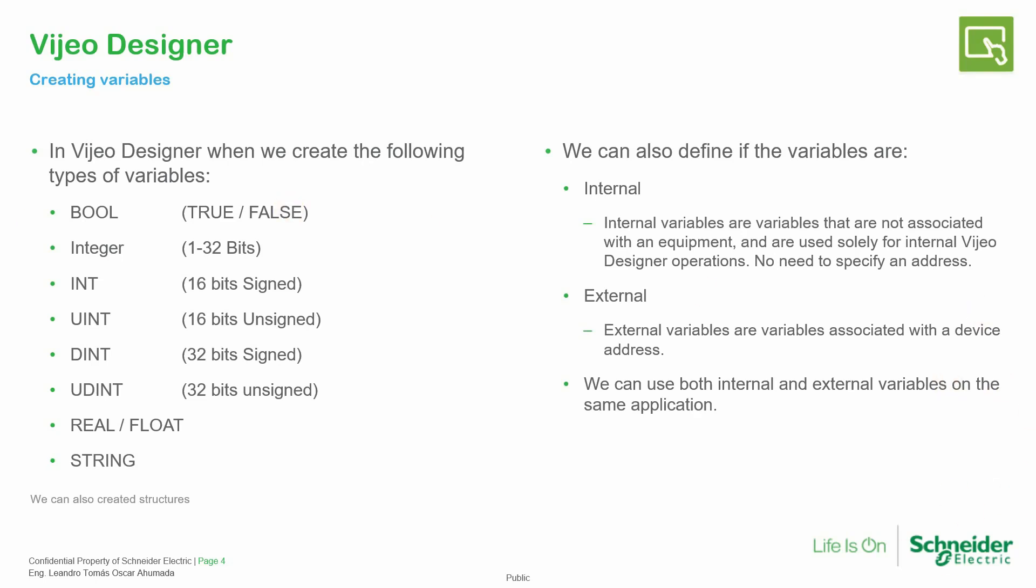These are the variables that we can create on Vijeo Designer. Most of them are in the PLC, and in the Vijeo Designer we have two different kinds of variables: we have the internals and the externals. The internals belong to the HMI and can be used inside the HMI like the local variables in the PLCs, and the external come from other devices. It's good to know that we can use internal and external variables inside the same project.